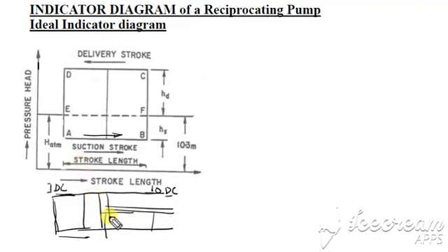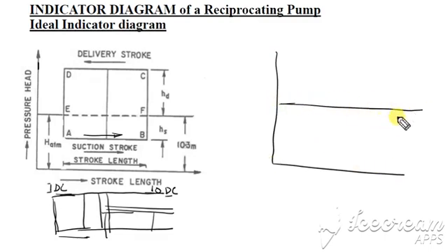Theoretically speaking or ideally, the pressure head in the cylinder of liquid entering the cylinder is assumed to be constant at a vacuum indicated by this height level. From the zero level this is this much height, but it is vacuum so it is below atmospheric. Atmospheric pressure head is shown as a reference. The atmospheric pressure head at this level, HATM in terms of meters of water column, is 10.33 meters of water.